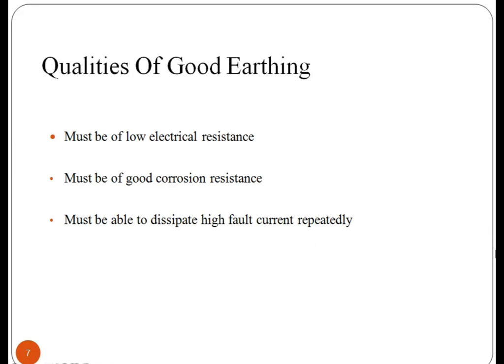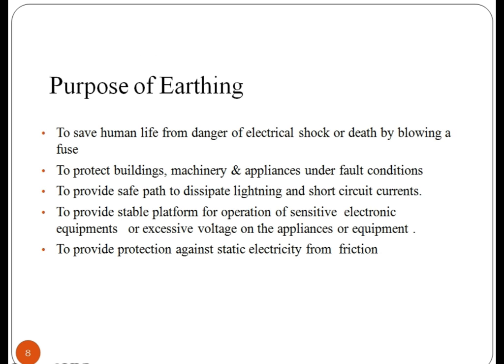What are the qualities of good earthing? An earth connection may serve a purpose other than shock protection and may normally carry current. The most important example of a functional earth is the neutral in an electrical supply system. Good earthing must have low impedance, enough to ensure that sufficient current can flow through the safety device so that it disconnects the supply. It has low electrical resistance and good corrosion resistance. It has the quality to throw away the high fault current repeatedly.